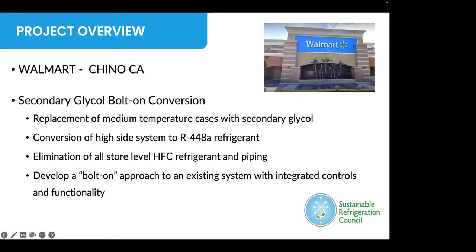It was originally a 404A store, and we converted that to an R448A refrigerant to minimize the GWP of the refrigerant that was going to remain in the store. But really, with putting in the medium temp glycol cases, that eliminated all of the store level piping that had HFC in it. And so it made a nice case study of getting a partial conversion to a low GWP or natural refrigerant, but it leaves a pathway for eliminating the HFC completely on the next subsequent projects at the store, because we've eliminated all of the HFC refrigerant on those systems inside the store.